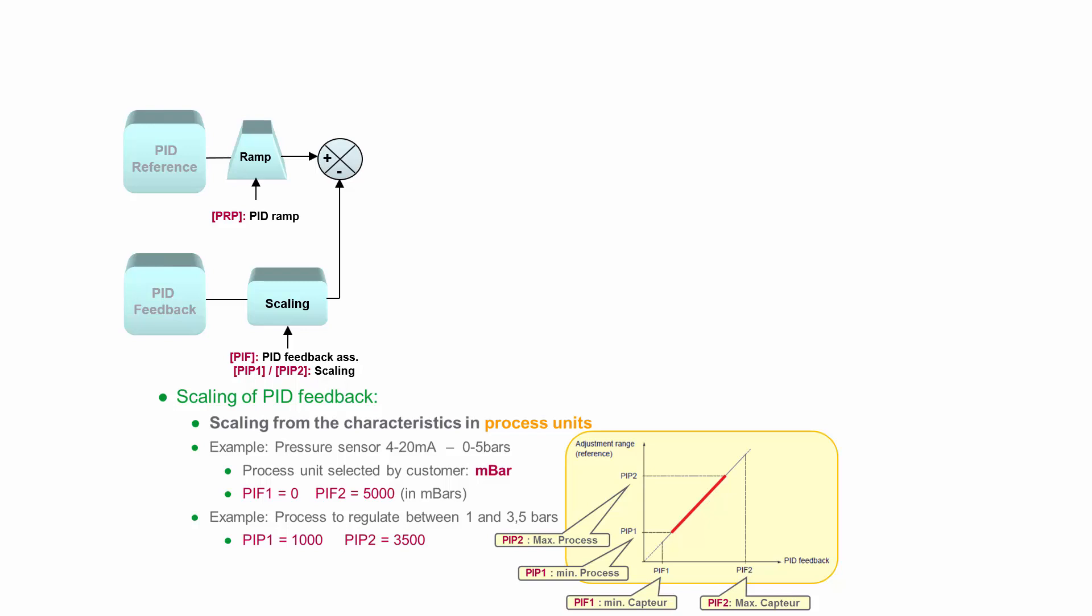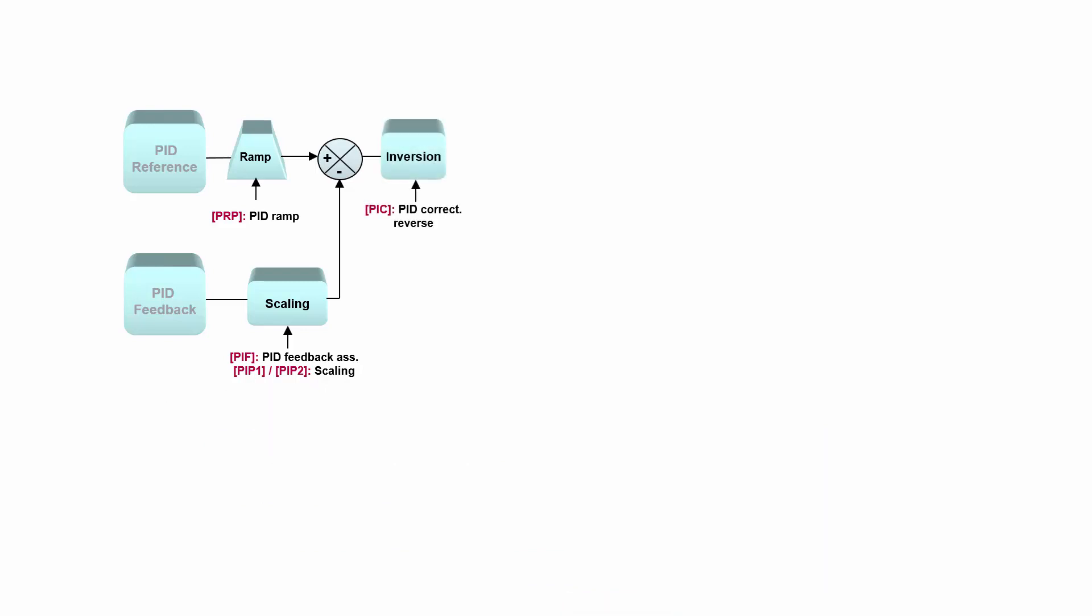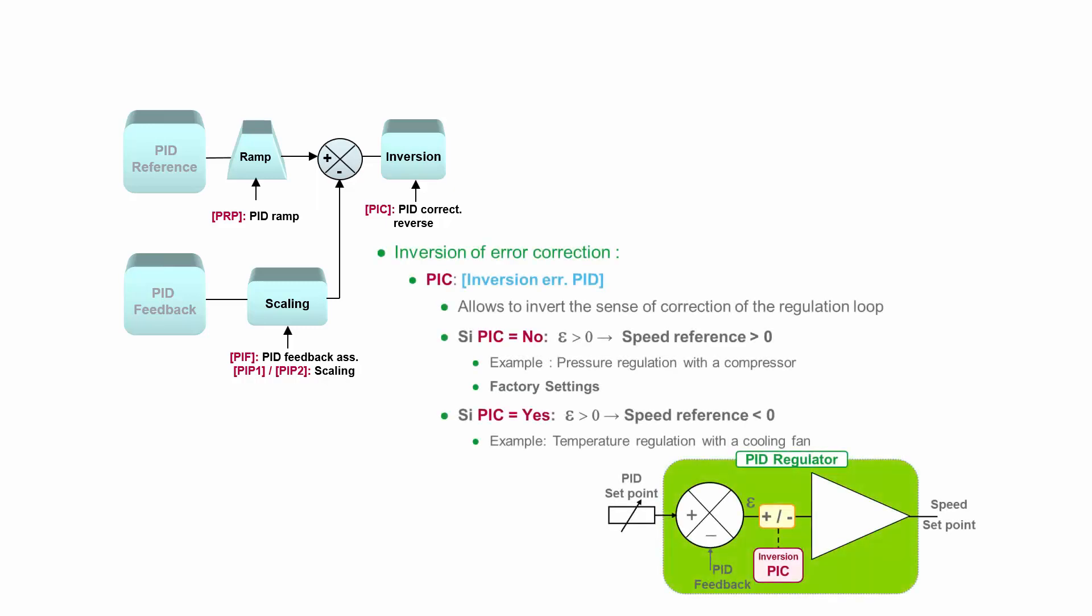After that we have error correction, and the first step of error correction is possibility to make inversion. Why would we need inversion? For example, if you have some compressor which is regulating pressure, then you will not inverse error correction. But for example, if you have some cooling application where you need to increase the speed of the fan if the temperature goes higher, then you need to inverse the error correction.